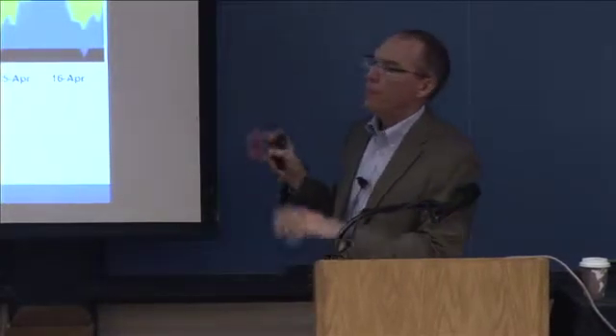So this dispatch stack on the right really captures the fundamental challenges of going to higher and higher renewables. You could imagine if we were at 50% or 60% wind, the problem only gets compounded. If we have dispatch stacks for those different penetration levels, the real transition from something that looks familiar and manageable to something a lot more alarming for a utility operator happens above 20%, somewhere in the 25 to 35% range, where it really starts to cut into the coal this way.